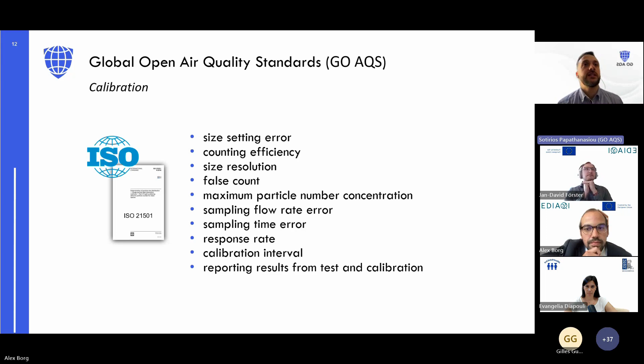There are some standards, like the ISO standards for particle counter devices or sensors, which have to follow specific thresholds across different categories, such as size setting error, count efficiency, size resolution, and whether they can count false particles. Something we don't have currently is widespread compliance - although not all, the majority of low-cost sensors do not comply with any standards currently.